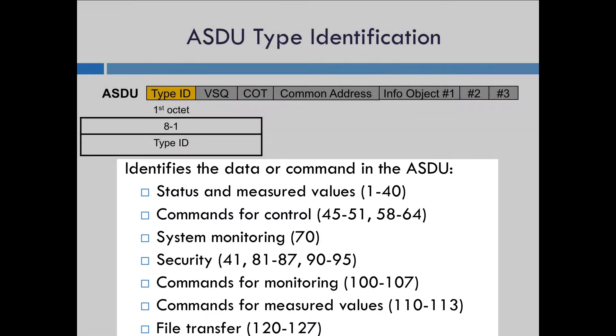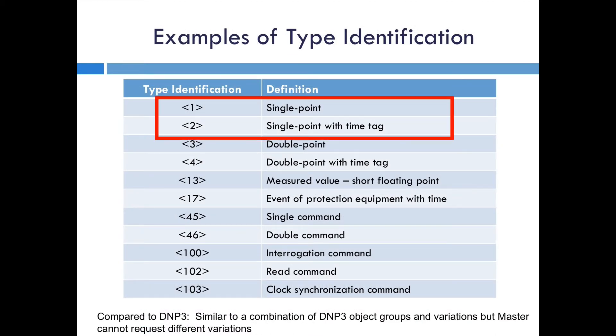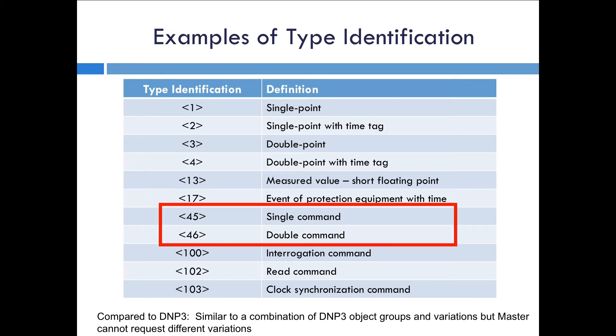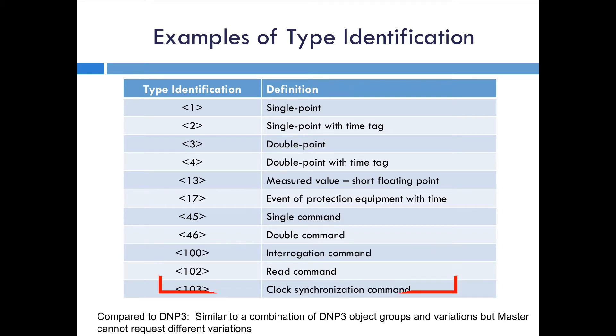Here are just a few examples: single point with or without time, double point with or without time, single point command, double point command, a read command, and clock synchronization. If you compare this to DNP3, it's roughly similar to the different object groups and variations, except it's fixed. With DNP, the master can request a specific object group or data type and a specific variation. With IEC 60870-5, it's fixed — the master cannot request different variations other than to request a specific type identification, and it gets the variation defined with that type.